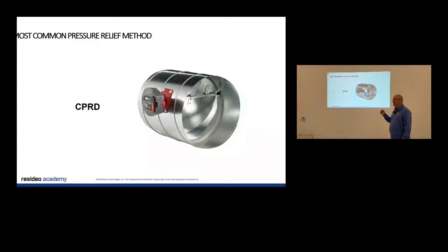And Paul kind of asked me to keep it somewhat simplified, but these normally will come out of the factory set correctly, because we're at a 1/2 inch of static and I'm not a duct designer, but 1/2 inch is what most heating guys try to size their ductwork to and get it correct. But if they need to, they come in, they open all the dampers, they shut the two biggest ones, so I'm trying to just feed the smallest one. If this damper doesn't open, all they do is crank that until it does, and they shut it and they're done. Takes about 2 minutes to set ours.